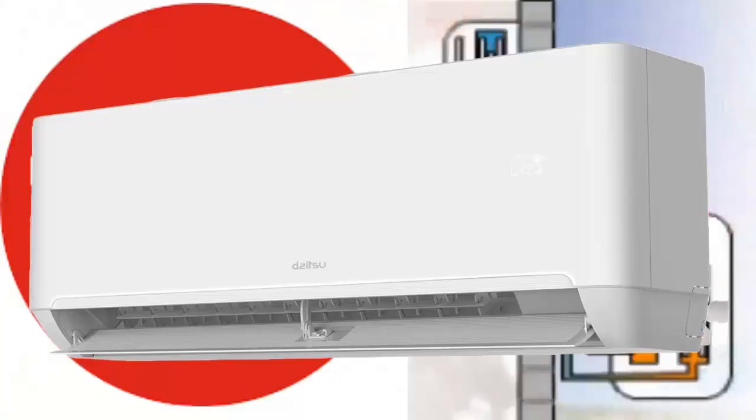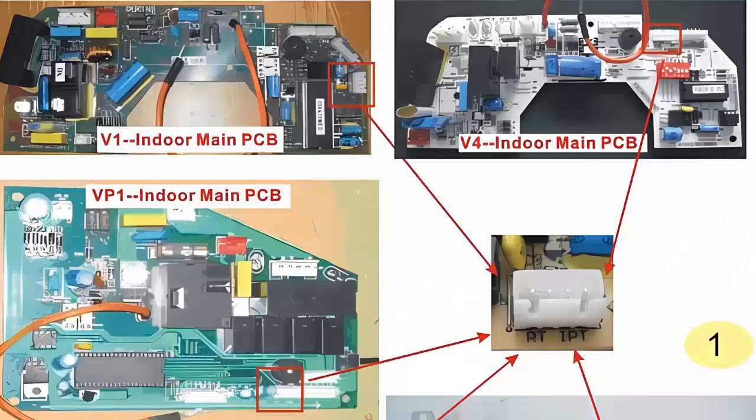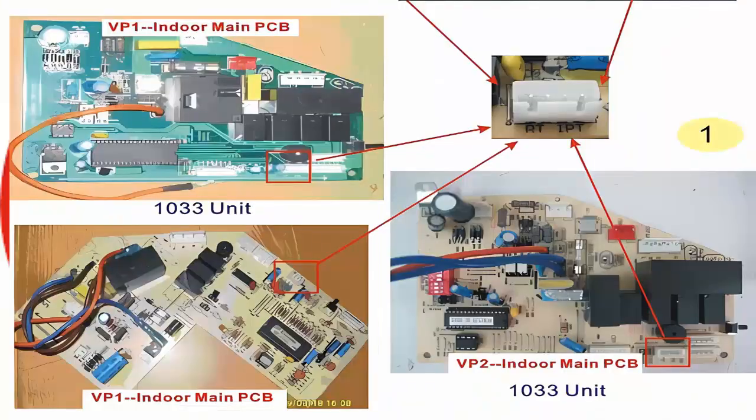3. Check the position and connection of the sensor located in the indoor unit's piping. Make sure that the coil sensor's connector is properly inserted into its slot. If it is loose, reinsert it firmly. Recognize the connector, as the connector for the ambient temperature sensor is also nearby. Turn on the unit and see if the error reappears.